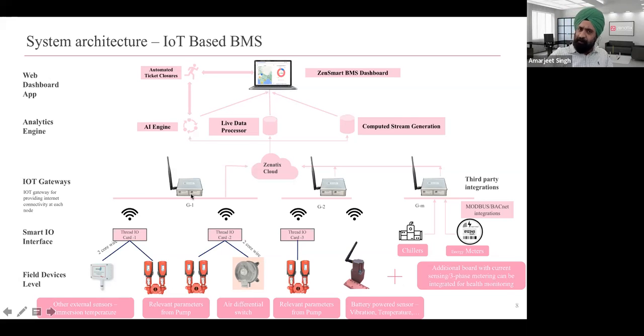An interesting thing at this gateway layer is that things are very different. Rather than wiring all the IO cards back within a large building or campus with multiple buildings to one central BACnet controller, you think of a large building as smaller zones. Each zone may have its own IO cards and one gateway, with the gateway directly communicating to the cloud.